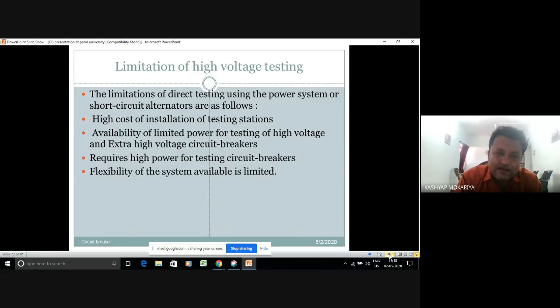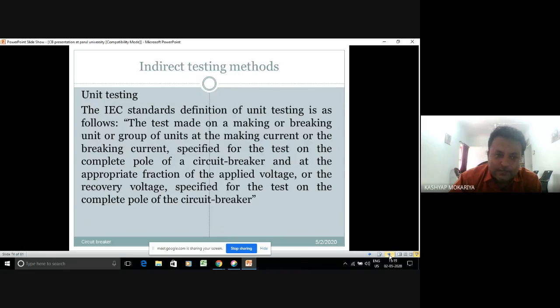There came the indirect testing methods. So the limitations of direct testing using the power system or short circuit alternator are as follows: high cost of installation of the testing station, availability of limited power for testing of high voltage and extra high voltage breakers, high power required for testing breakers, and flexibility of system availability is limited. So, unit testing. The IEC standard definition of unit testing is as follows: the test made on a making or breaking unit or a group at the making current or breaking current specified for the test on the complete pole of the breaker.